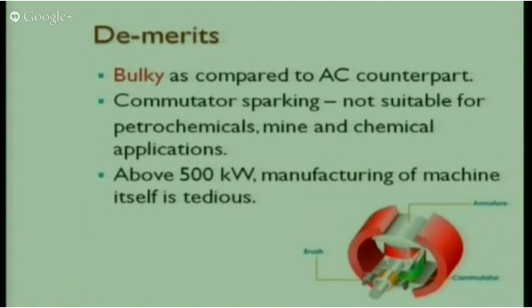And that's a constant sparking. So what will be the problem with constant sparking? It is all the time power loss, that is one thing. Second thing, its life reduces slowly because of pitting. So pitting, you understand, carbon deposition will keep happening. The more sparking there is, the more carbon deposition there will be on it. And ultimately a small pit-like hole forms, which is called pitting. And that will cost its life. So performance will automatically reduce. This is one major disadvantage.